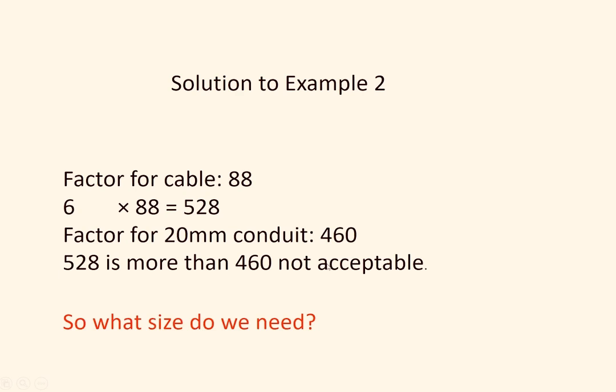And so the solution to that is the factor for the cable is 88. We've got 6 88s, gives me 528, and the factor for the conduit was 460. So the answer is no, it's not acceptable anymore. Again, not saying that it physically wouldn't fit, but that cable wouldn't be able to cool itself. The grouping factors and the temperature are going to be impacted quite badly.